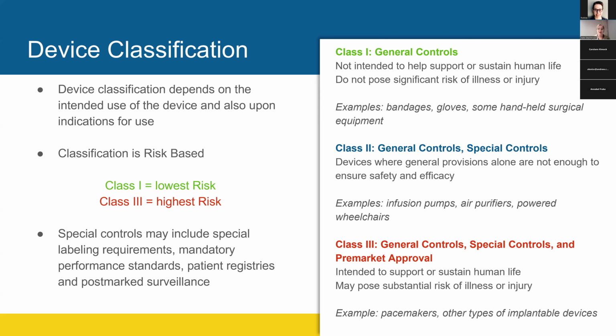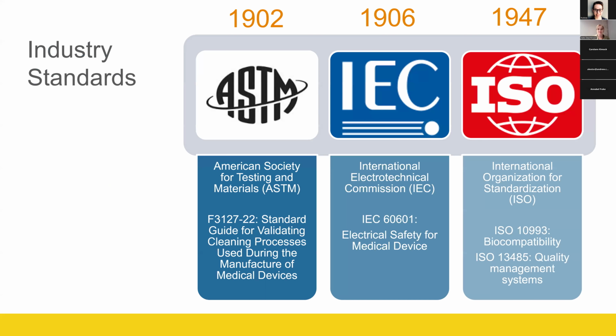And they meet their specifications. General controls, once you add special controls, that's where you get into, okay, do you have to have calibration? Do you have to check they're measuring things correctly? Are there sharp edges? Are there potential ways this could really hurt somebody? And do you have ways to mitigate that? And then for class 3, you not only have general controls and special controls, you have additional potential controls that are part of the FDA approval.